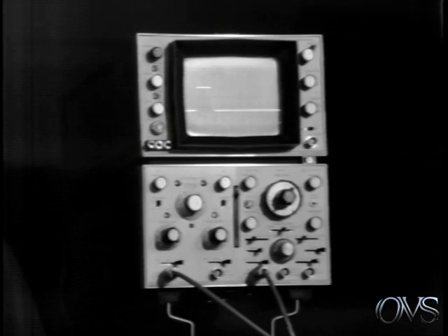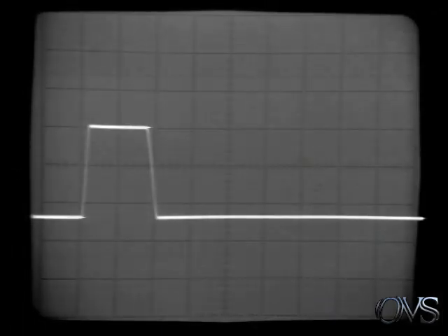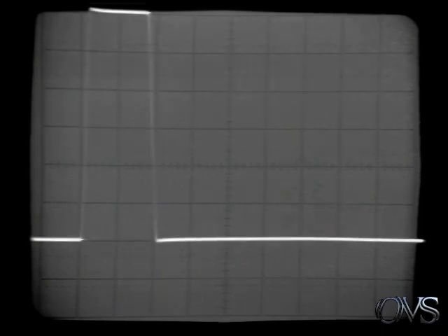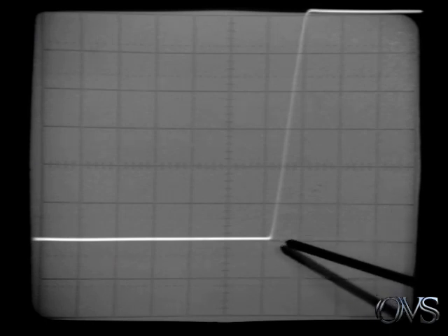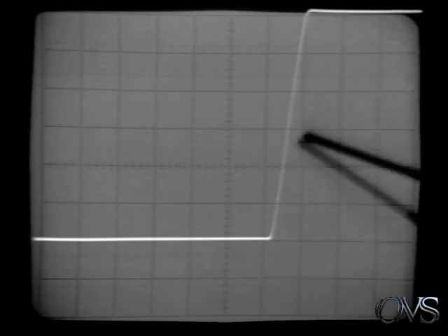Now let's focus our attention on the third major capability of a delayed time-based generator. Since the conception of an oscilloscope, it's been used to make time measurements as well as amplitude measurements. And with a single time-based generator, the oscilloscope was used to make time measurements by simply comparing the waveform to the graticule on the CRT. For those time measurements, since the sweep was calibrated, the operator could obtain a measurement of time comparing the waveform to the graticule. And in present-day oscilloscopes, the accuracy of that measurement is typically plus or minus 3%.